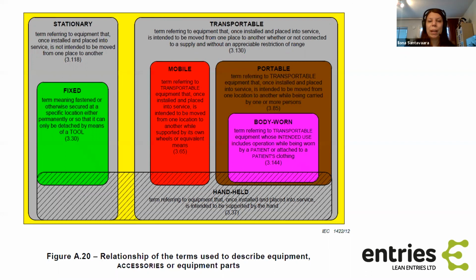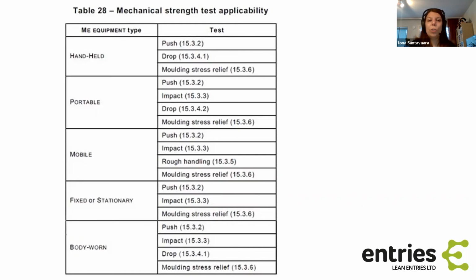So that is the handheld part. And then if you are going over the requirements and the test requirements, you have, of course, all the requirements for the fixed equipment, but then you also need to consider for that remote part those handheld equipment test criteria and requirements. And then these definitions would, for example, affect this table. So mechanical strength test applicability. So which mechanical strength tests you would need to do. So for handheld, you would need to do push, drop and molding stress relief test. And then again, for something like mobile, it would do push, impact, rough handling, and molding stress relief. So this is just one point and example in the standard where any classification affects what you need to do or what you need to test.